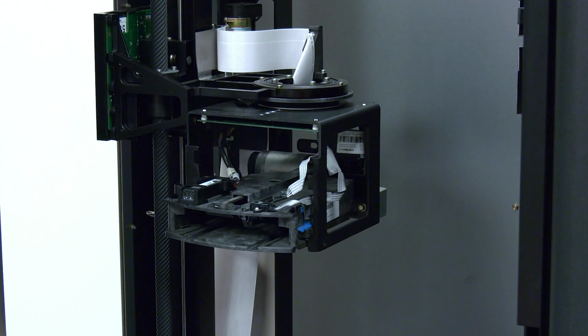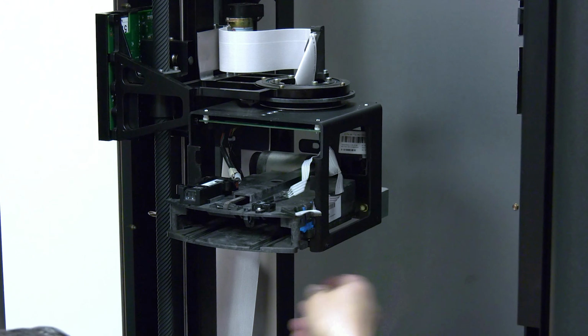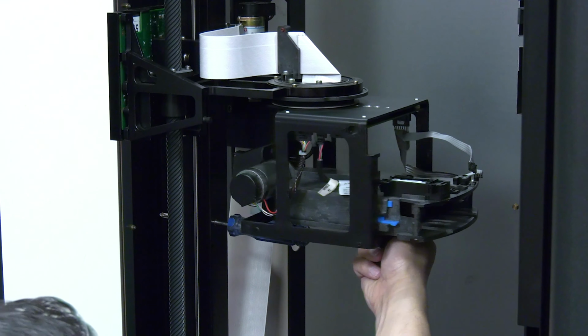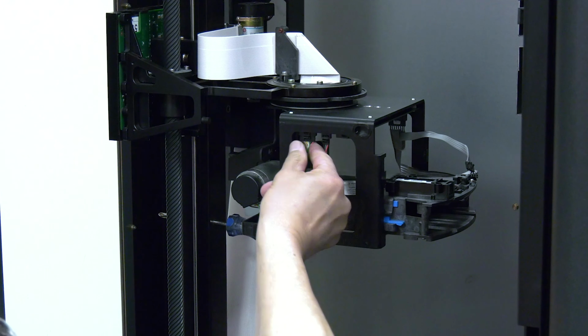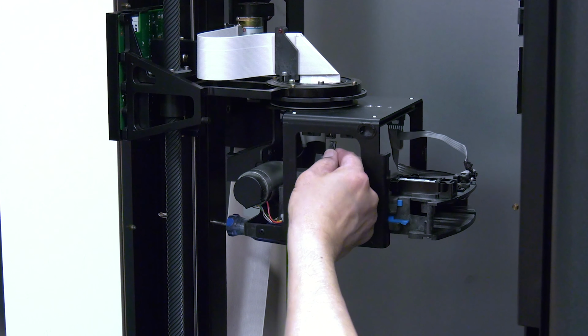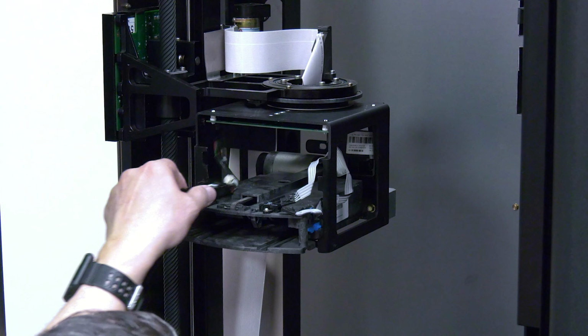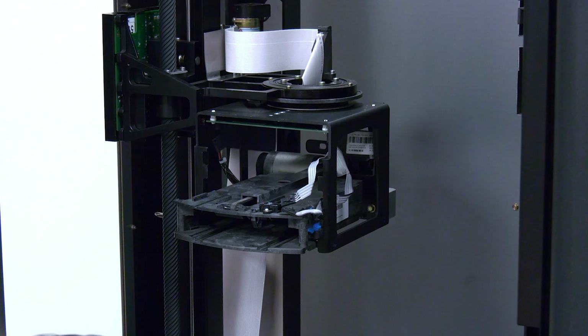To remove the bottom gripper, you will start by performing the same first few steps as the top gripper. Undo the front sensor and then slide motor along with the first blue slide lock. Then, while you are still on the first side, you also need to undo the calibration sensor from the gripper frame and then slide the calibration sensor forward and off the bottom gripper and set it to the side to be reinstalled on the replacement.